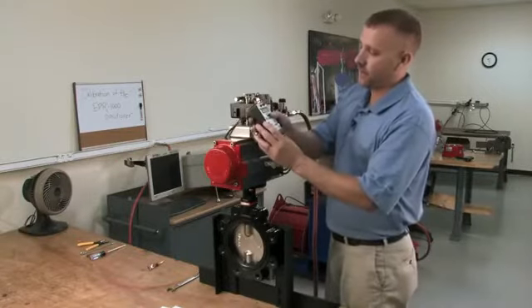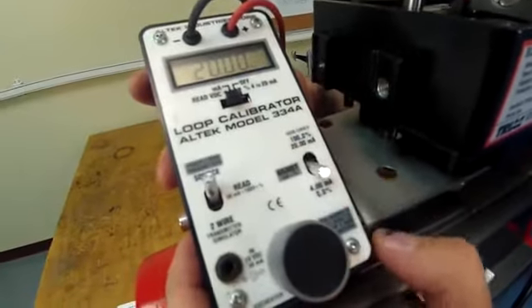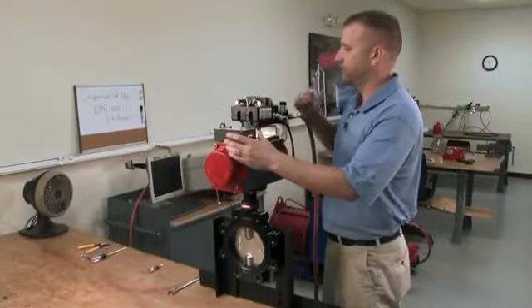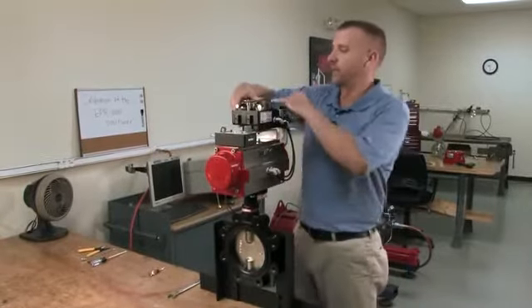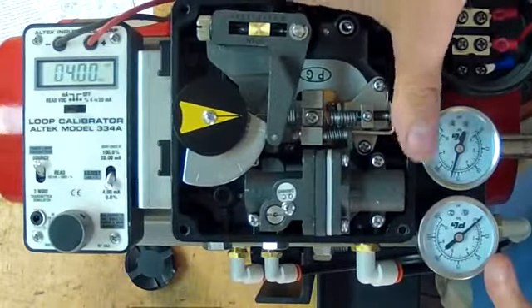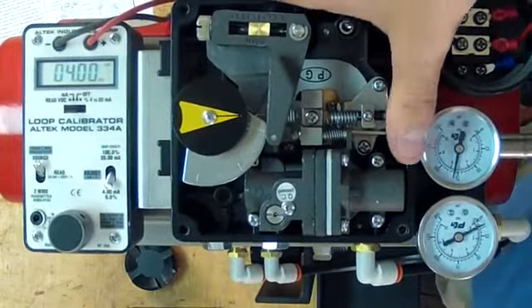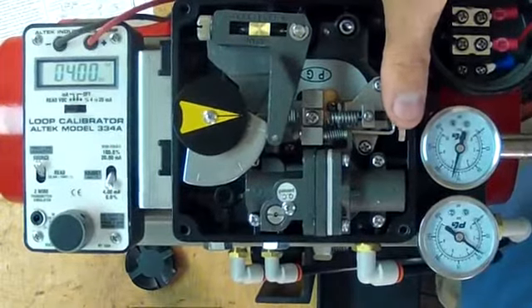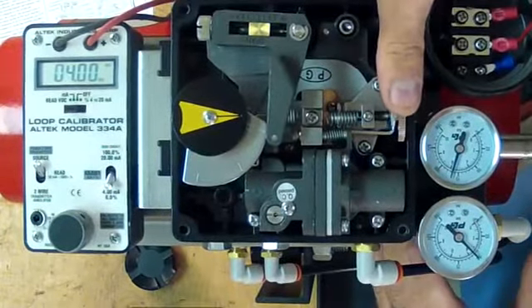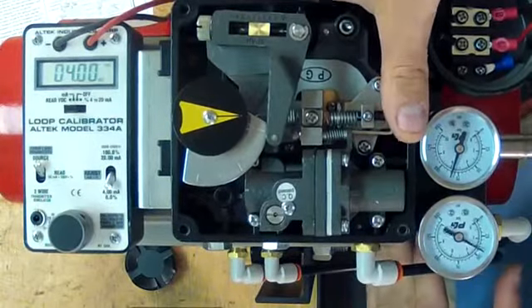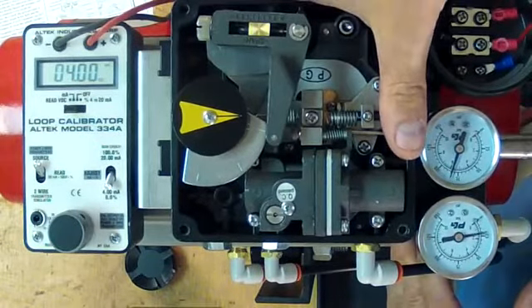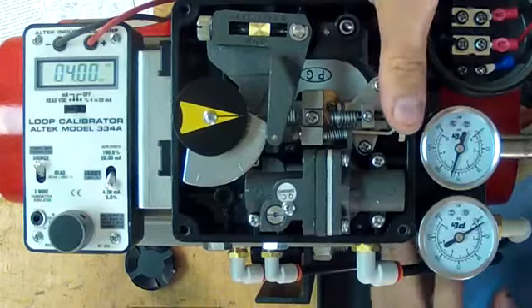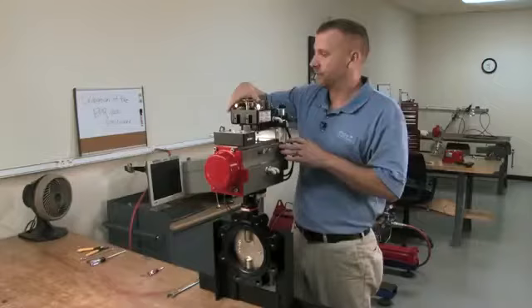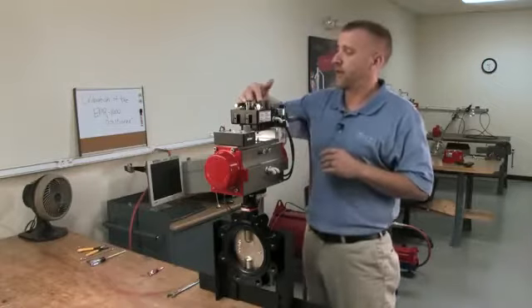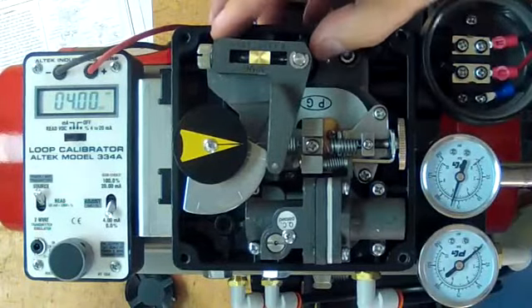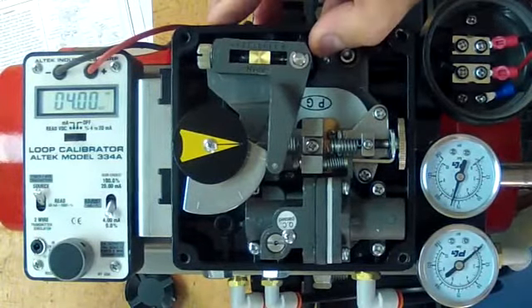Now, turn your calibrator on. I'm going to start at our 4 milliamp position. And what you do is you adjust your thumb screw clockwise till the gauge begins to climb. And once you notice it's climbed, you back it off counterclockwise till it falls nice and slow down to the 0 position. One other thing about this positioner is your 0 and your span are interactive. That means if you adjust one, you typically have to adjust the other.